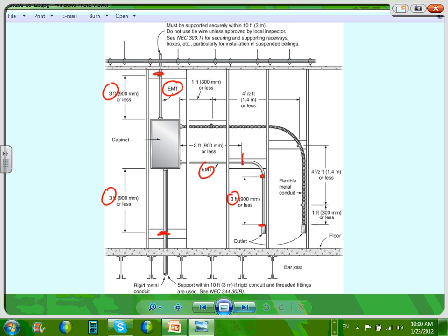For most of the conduit, with some exceptions, I'm not going to get into the details, but for most of the time, first, you walk into any conduit, make sure it's supported within 3 feet. This one right there, it's supported within 3 feet, right? Within 3 feet means 3 feet or less, and every 10 feet intervals.